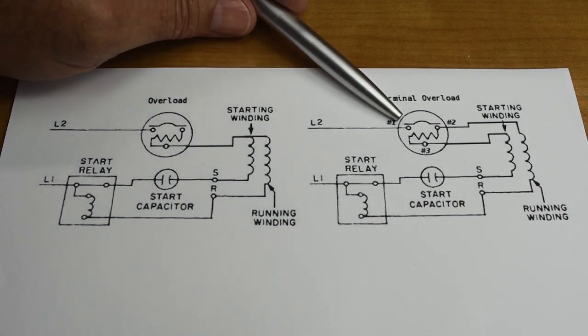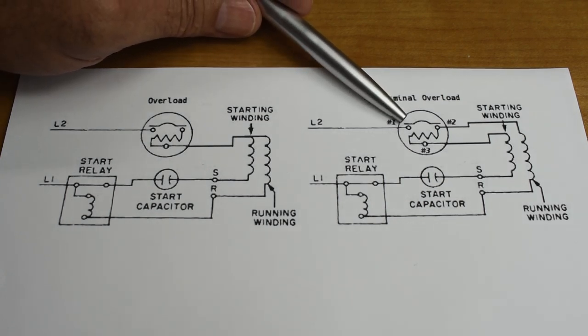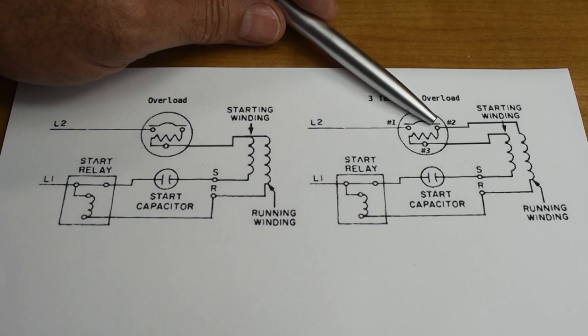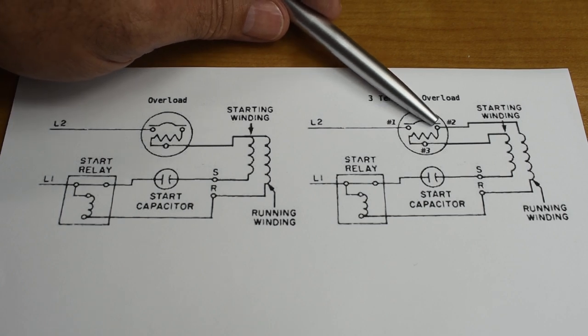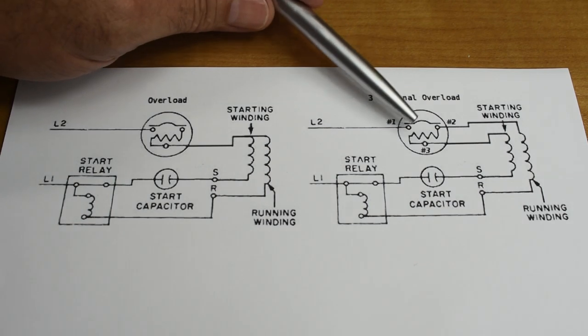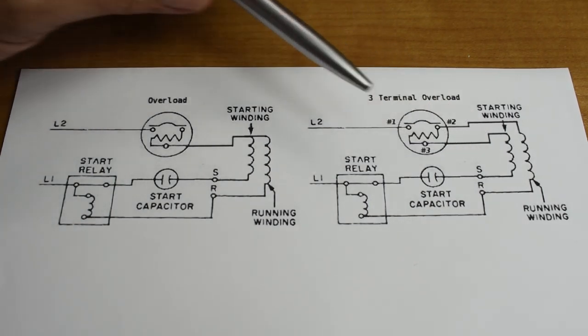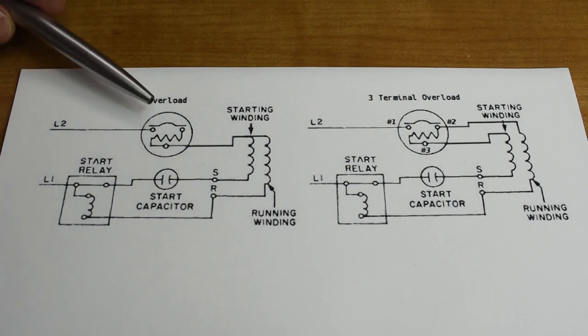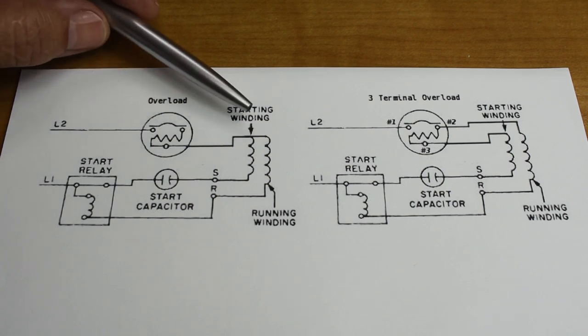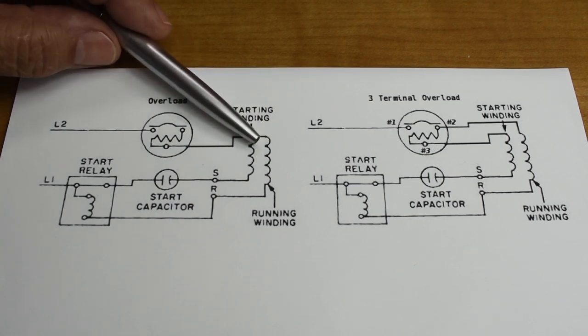On this one here with 3 wires, current flows in across the opposite side, and then the run winding is connected to pin 2. And then the start winding is connected after the resistive element. The only way this is going to open up the circuit is if there's an excessive load placed on the motor, causing more current to be drawn by the motor and increasing the level of heat.